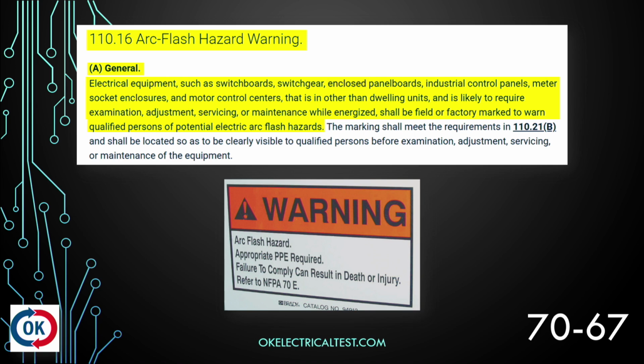And so letter A, general. Electrical equipment such as switchboards, switchgear, enclosed panelboards, industrial control panels, meter socket enclosures, and motor control centers that is other than a dwelling unit and is likely to require examination, adjustment, servicing, or maintenance while energized shall be field or factory marked to warn qualified persons of potential electrical arc flash hazards. So, if there is a potential for an arc flash hazard, we need to have some sort of warning sign on or adjacent to the equipment.